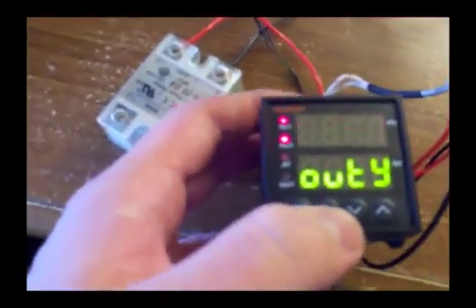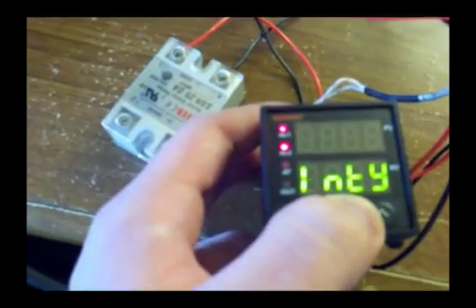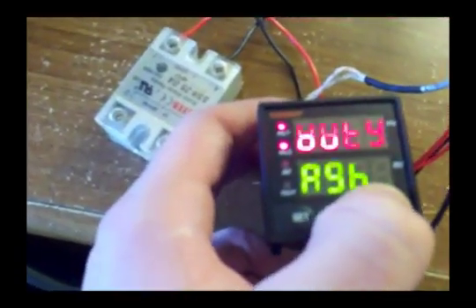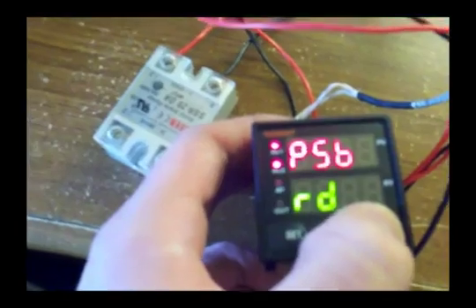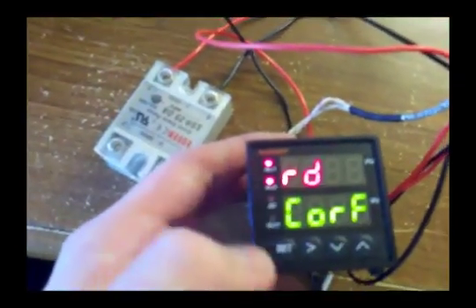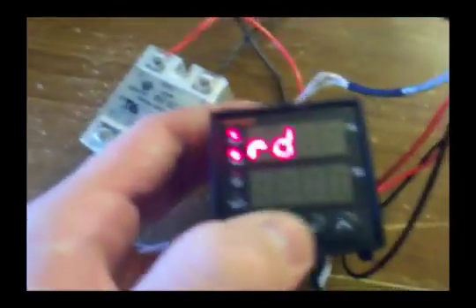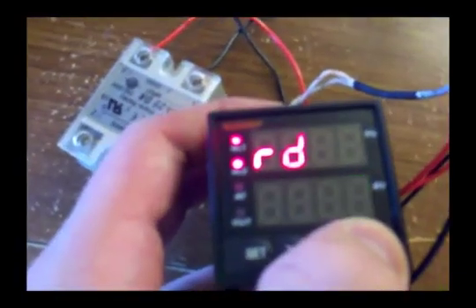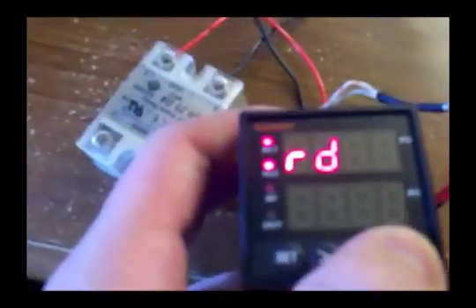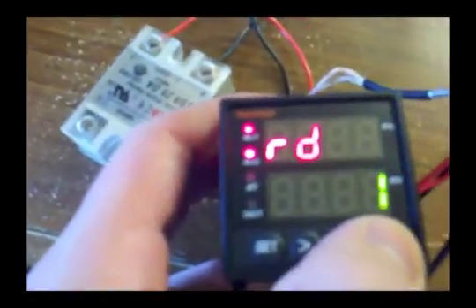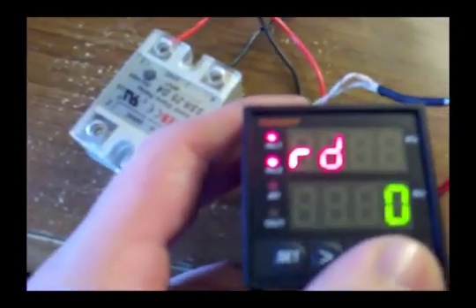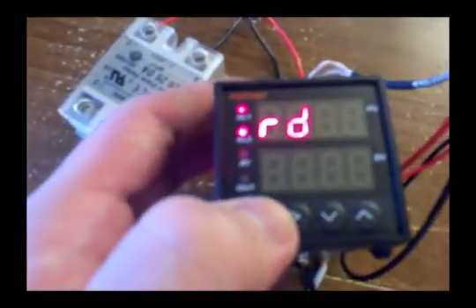Press select. You don't really need to mess with out. Go up. You don't need to mess with that. You don't need to mess with that. You don't need to mess with that. You do need to mess with R, D. R, D has two values, 0 and 1. If it's at 1, that means you're using this to cool stuff down. If it's set at 0, it means you're using this to heat stuff up. So I'm going to leave it at 0.